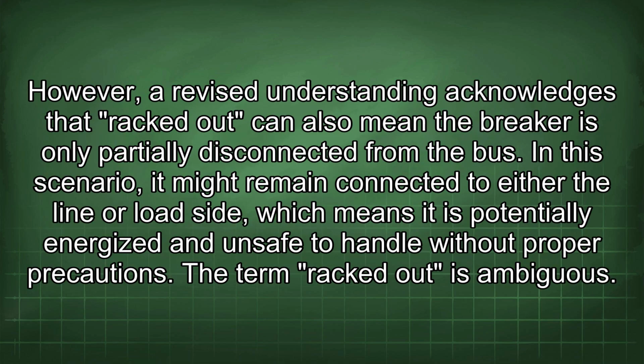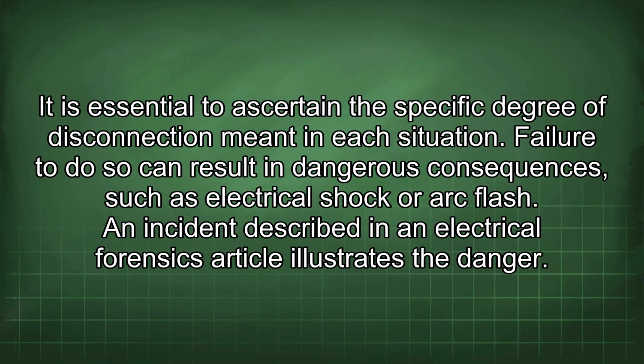However, a revised understanding acknowledges that racked out can also mean the breaker is only partially disconnected from the bus. In this scenario, it might remain connected to either the line or load side, which means it is potentially energized and unsafe to handle without proper precautions. The term racked out is ambiguous. It is essential to ascertain the specific degree of disconnection meant in each situation. Failure to do so can result in dangerous consequences, such as electrical shock or arc flash.